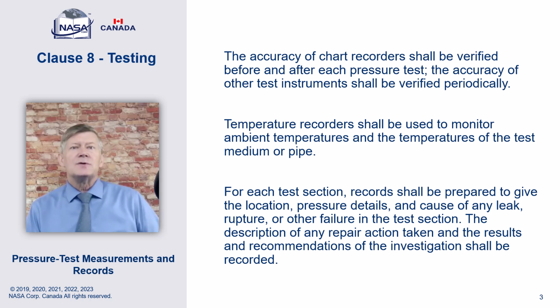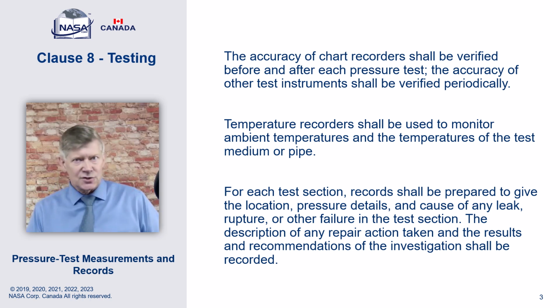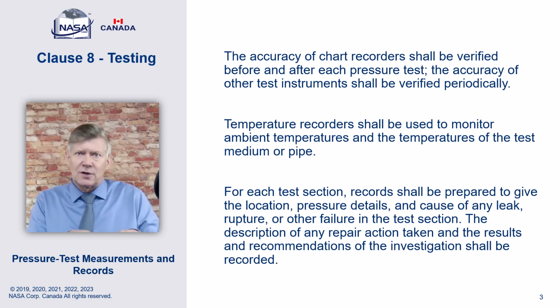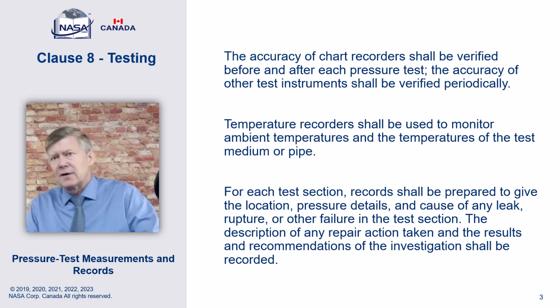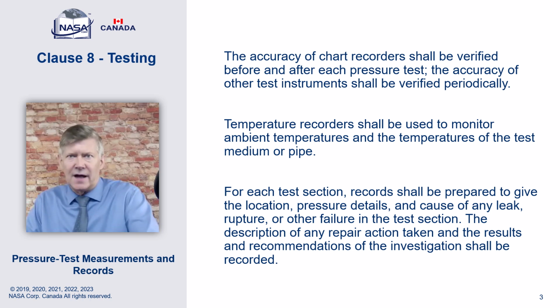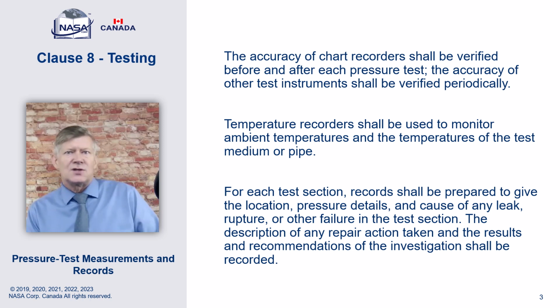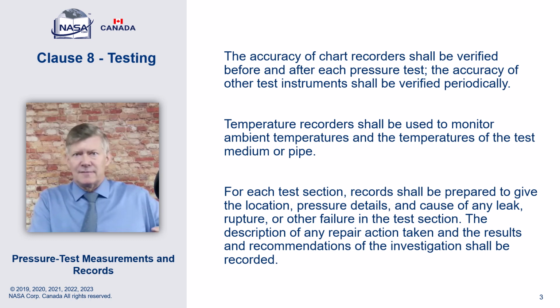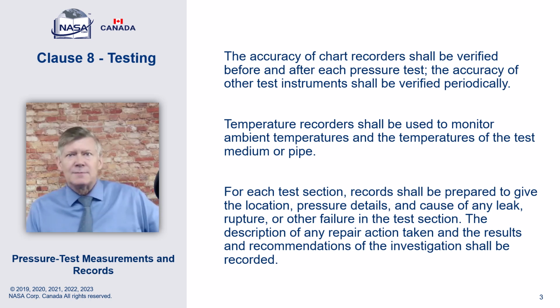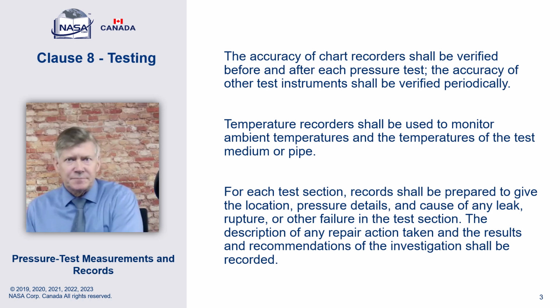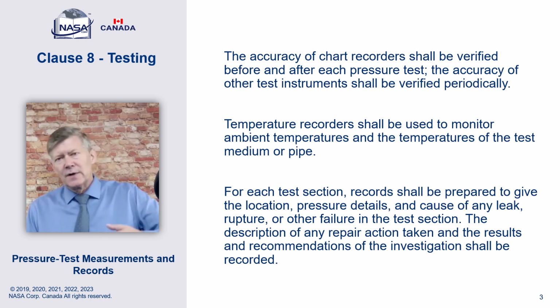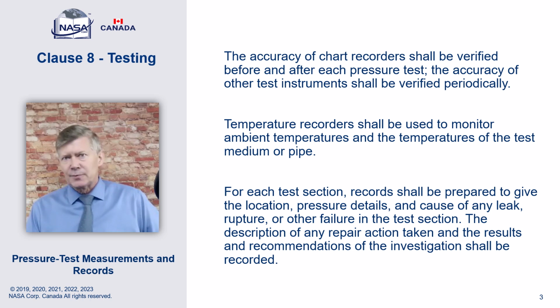Okay. Now, what a lot of companies do is they'll run 2 chart recorders. Okay, and most jurisdictions will accept this. If I verify that 2 chart recorders are working correctly, take them out into the field, do my test, and through the test they read identical, right? Statistically, that means I'm fine, because the chance of 2 instruments failing in exactly the same manner simultaneously, right? You've got a better chance of being hit by lightning 3 times in a row. Like, it's just statistically almost not possible. Okay, so that rationale is used, and that's why in the field you most typically see multiple chart recorders, right?